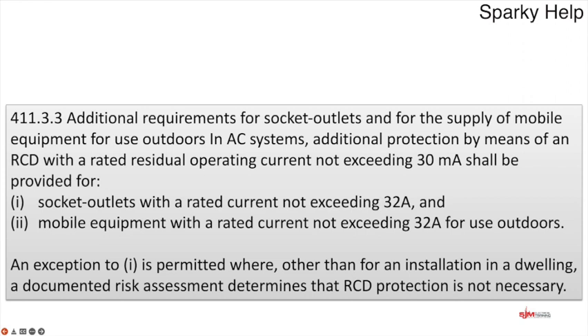So if we were in a commercial installation, you had 32 amp sockets, the top bit of the regulation basically says you should put a 32 amp breaker on it, or protective device, so up to that size, and it should have a 30 milliamp RCD. You could choose not to. If you choose not to, you have to then attach the corresponding risk assessment explaining why you've felt that you do not need it. Why you'd bother going to these lengths, I do not know. So it's probably just easier to put it in and save yourself some unnecessary paperwork.